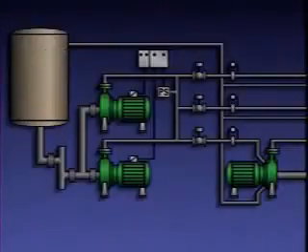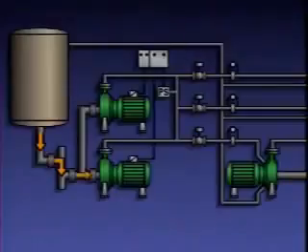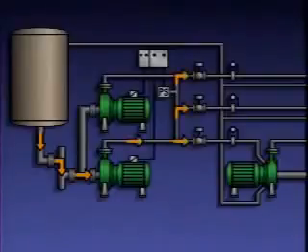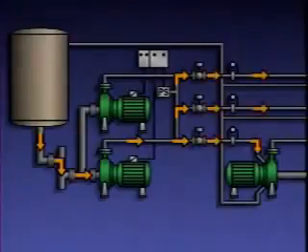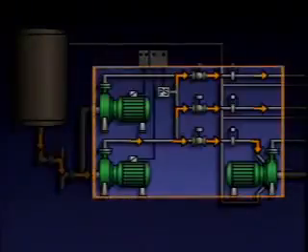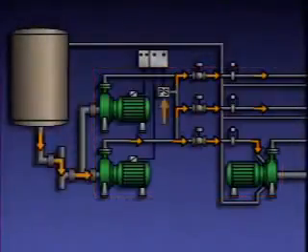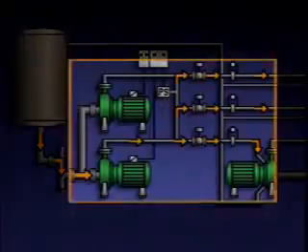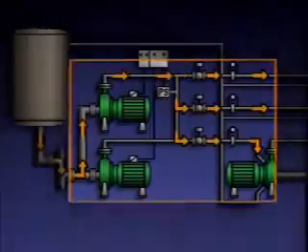During operation, the supply pump draws oil from the storage tank through the filter. The filter removes contaminants from the oil to prevent damage to the sealing system pumps and the mechanical seals being supplied. The pump supplies oil to the pressure regulators on each supply line, which control oil pressure and the amount of oil flow to each mechanical seal. The flow meters allow the flow to the seals to be monitored. If the supply pump fails to deliver oil at the correct pressure, the pressure switch will automatically start the backup supply pump to restore pressure.